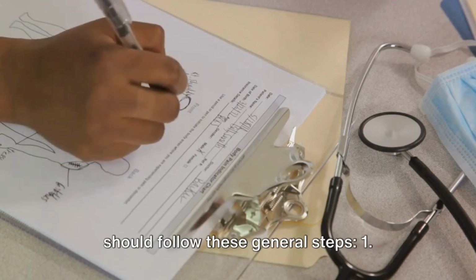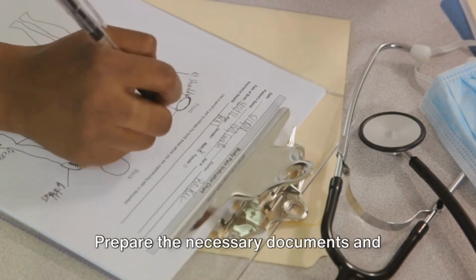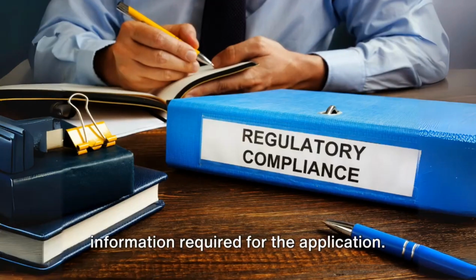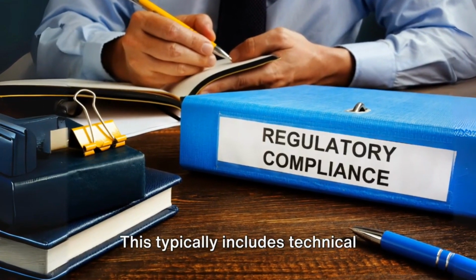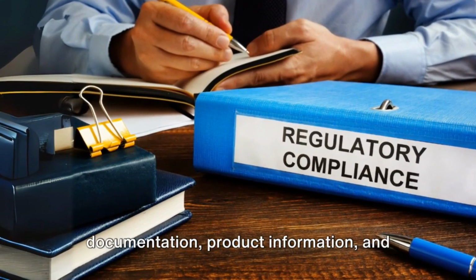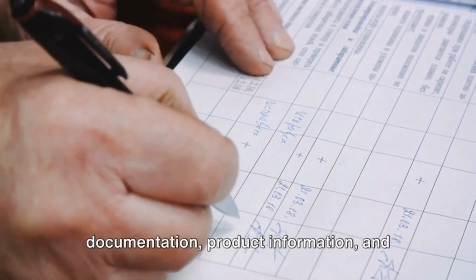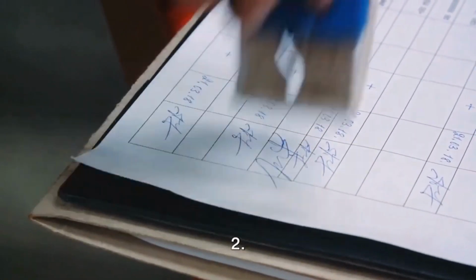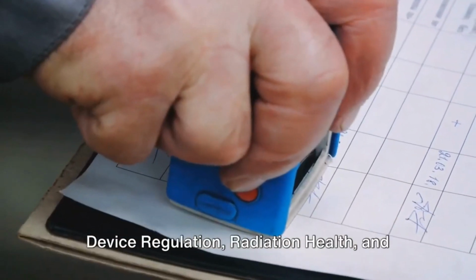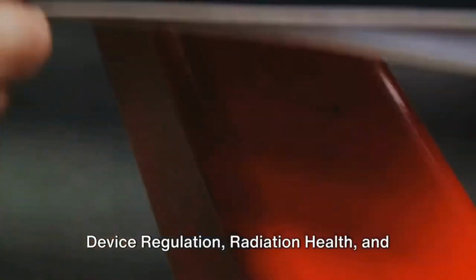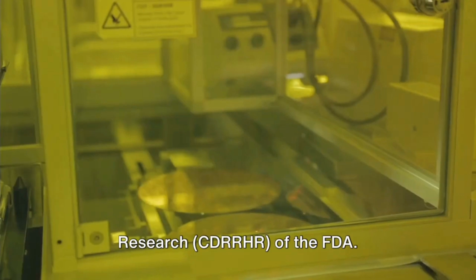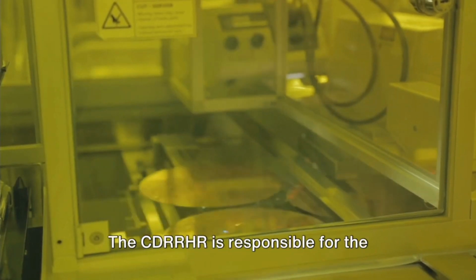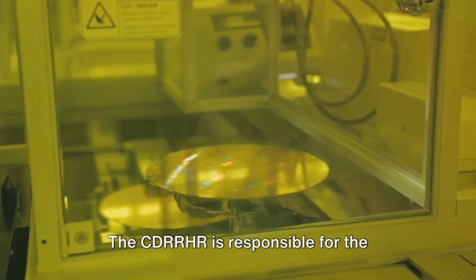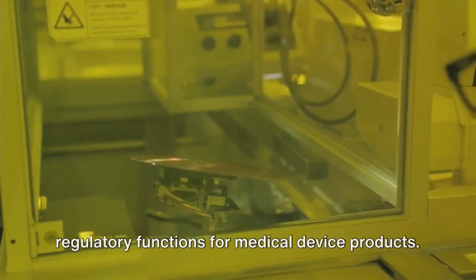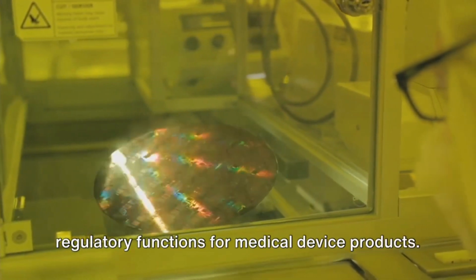To apply for a Certificate of Product Registration, or CPR, under the Philippine Food and Drug Administration, or FDA, you should follow these general steps. 1. Prepare the necessary documents and information required for the application. This typically includes technical documentation, product information, and proof of compliance with relevant regulations. 2. File the application at the Center for Device Regulation, Radiation Health, and Research of the FDA. This office is responsible for the regulatory functions for medical device products.